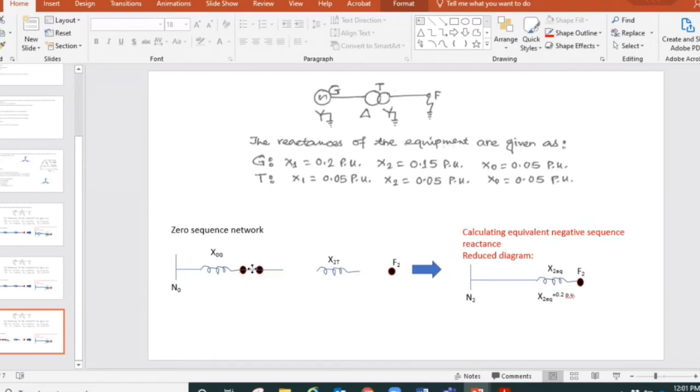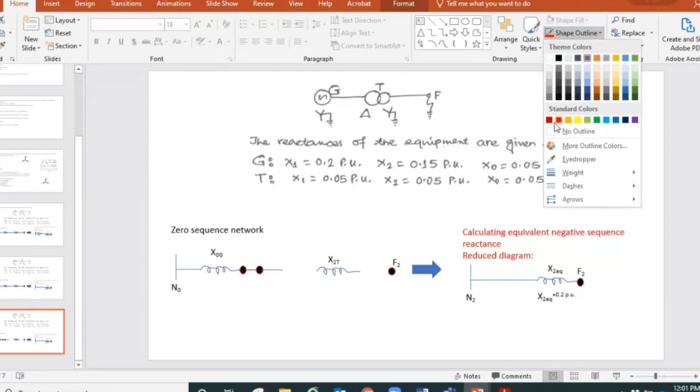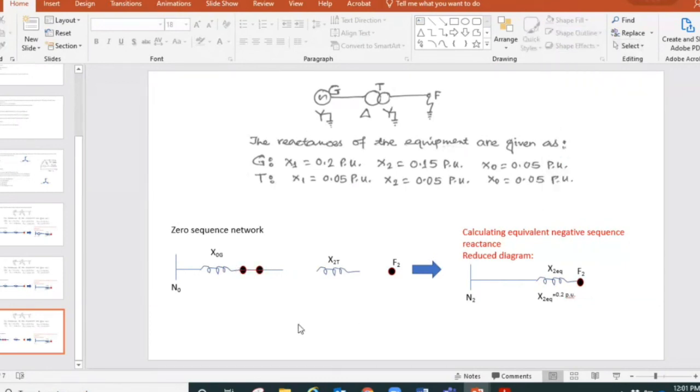We initially leave it open, but after looking at the connection and applying the theory that we have learned, I put it in red so that we know that we started with open and then we closed it, looking at star connected grounded solidly, so the zero sequence component of current in the lines can flow. So that's why I closed it, because it can flow.